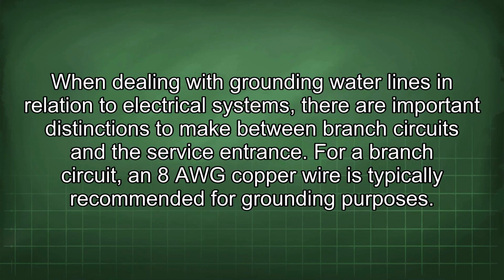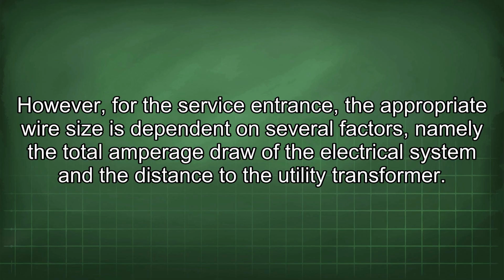When dealing with grounding water lines in relation to electrical systems, there are important distinctions to make between branch circuits and the service entrance. For a branch circuit, an 8 AWG copper wire is typically recommended for grounding purposes. However, for the service entrance, the appropriate wire size is dependent on several factors, namely the total amperage draw of the electrical system and the distance to the utility transformer.